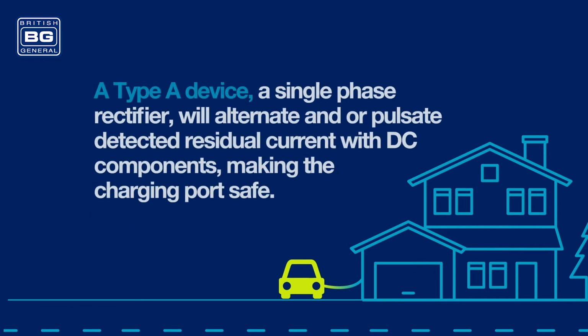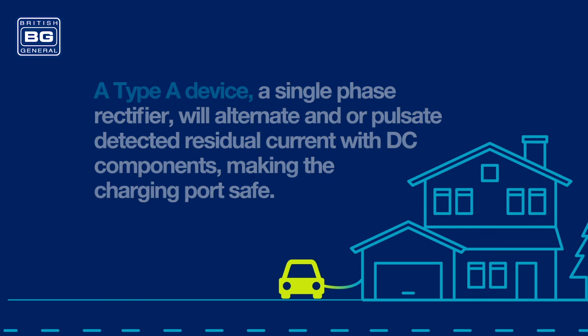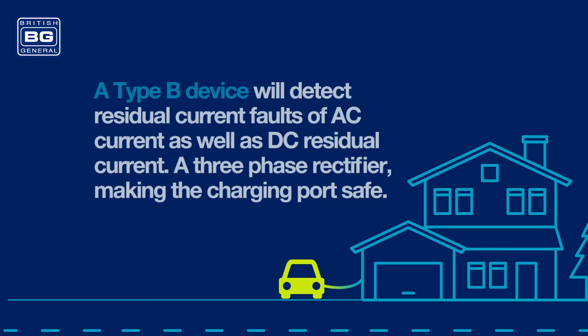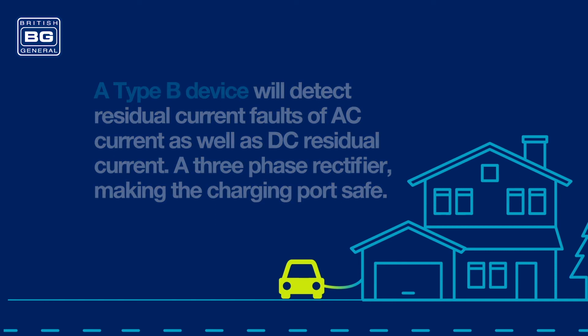A Type A device, a single-phase rectifier, will detect alternating and/or pulsating residual current with DC components, making the charging port safe. A Type B device will detect residual current faults of AC current as well as DC residual current, a three-phase rectifier, making the charging port safer.